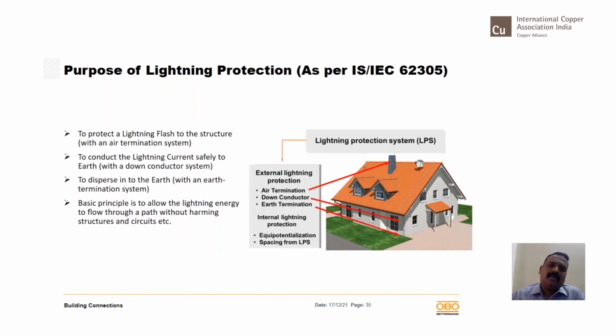Right. So what is the purpose of lightning protection as IEC defines it? It is to protect the structure against a lightning flash with an air termination system. Remember, the air termination can be horizontal or vertical depending upon the building dimensions, size, and the nature of the structure. Then, to conduct the lightning current safely to earth with the help of a down conductor. Thirdly, to disperse the current into the earth. So the basic principle is to allow the lightning energy to flow through a path without harming the structure or the circuits inside the structure.